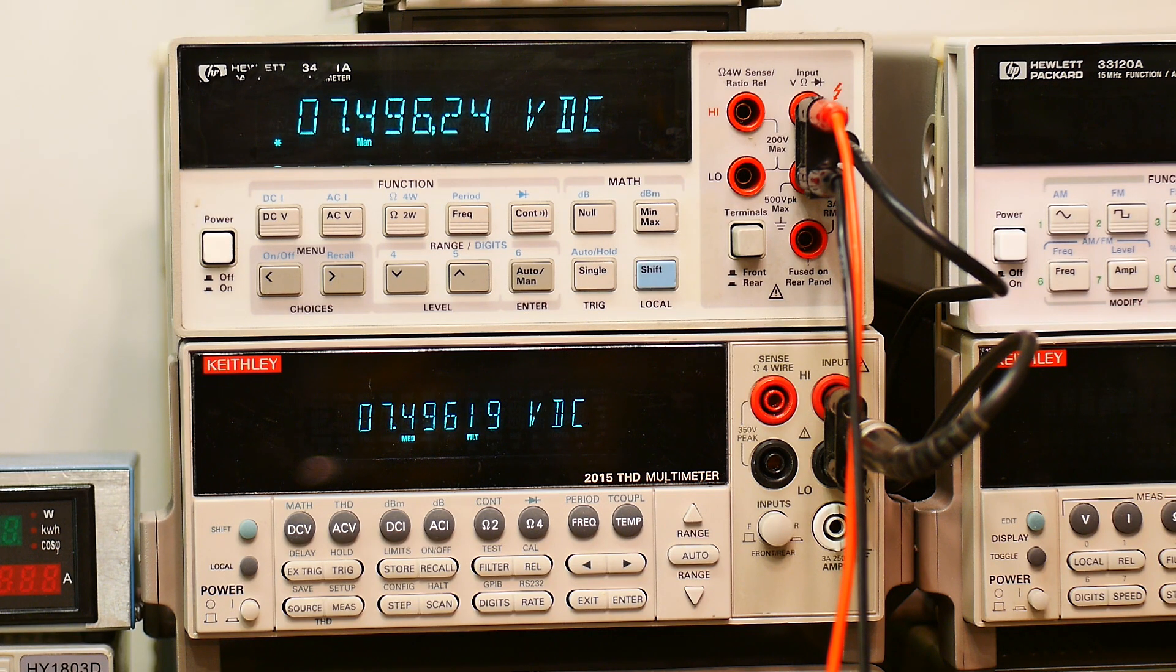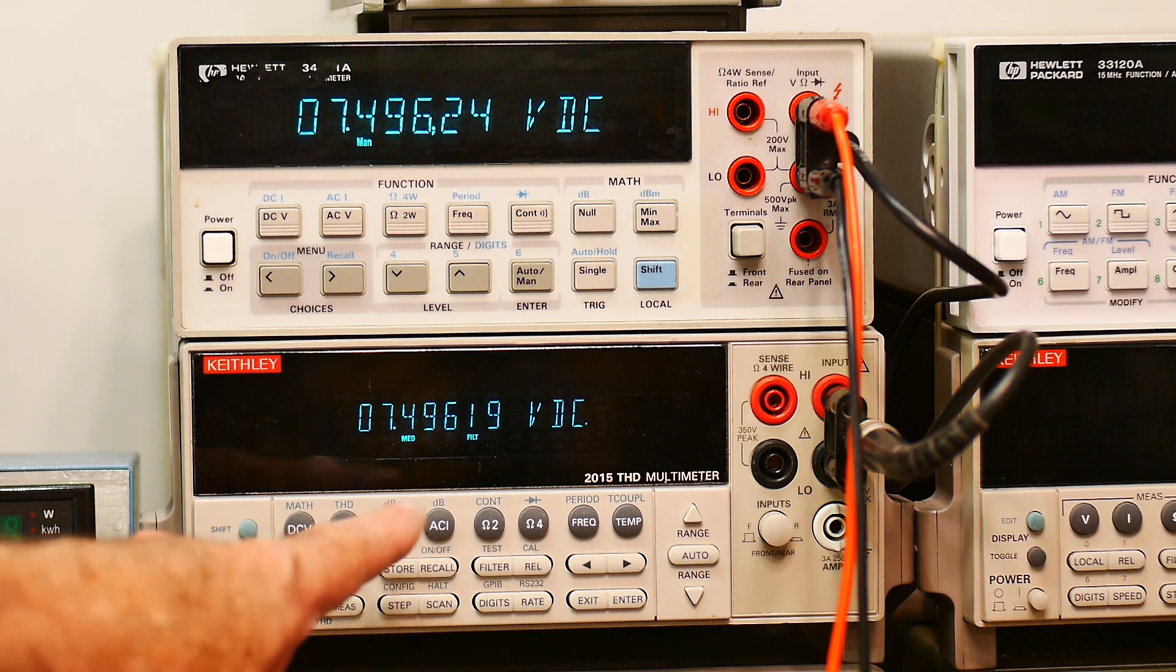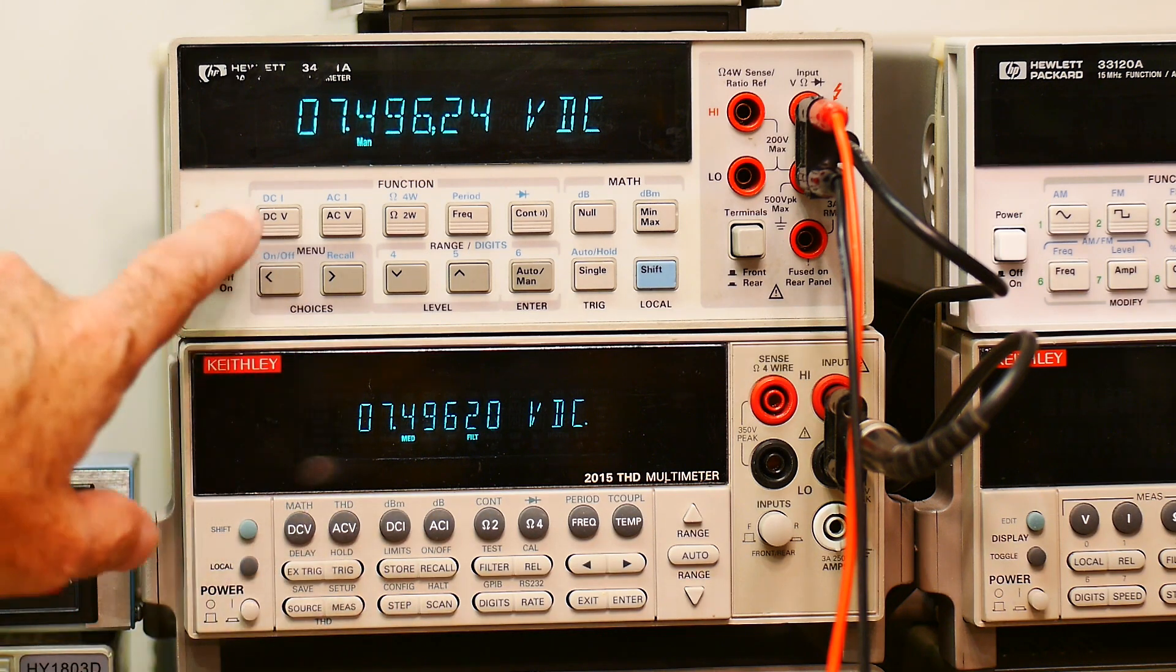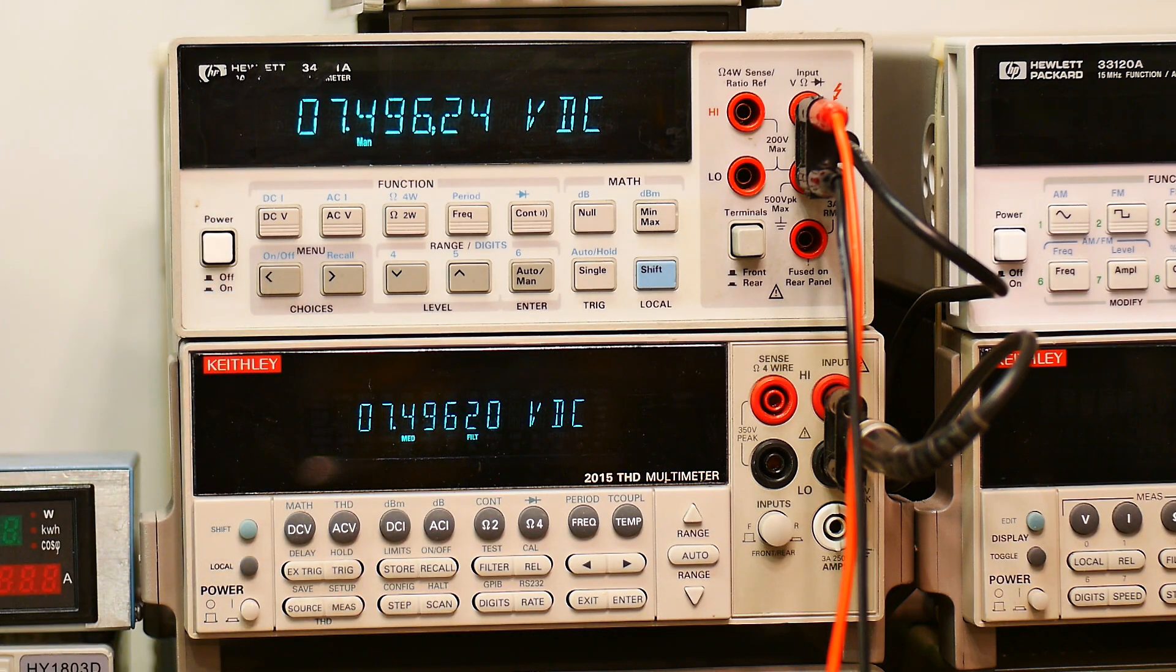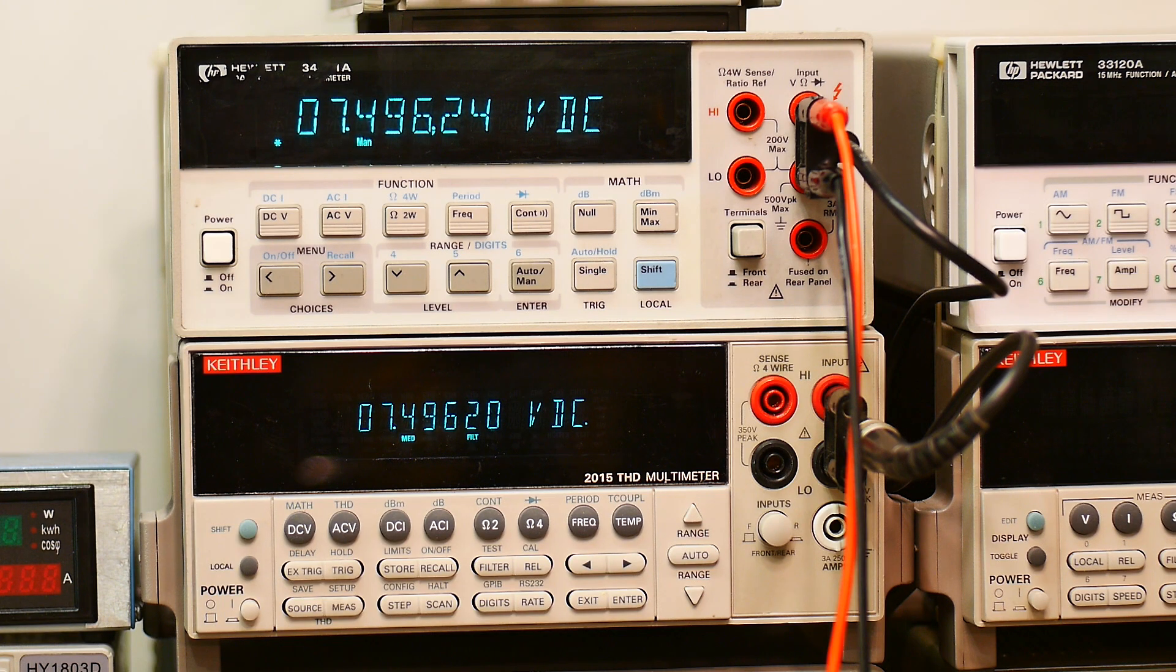And they are agreeing within a couple counts. This one looks like it hasn't drifted as much. Now this one should be 7.49618, 618, 619. Yeah, this one is staying better spec than the HP one. Keithley's doing a little bit better.